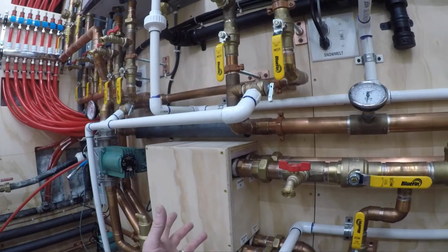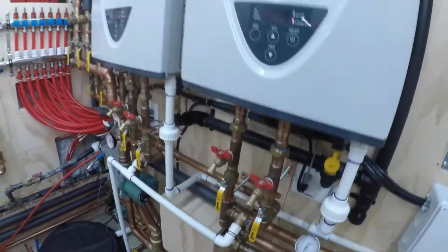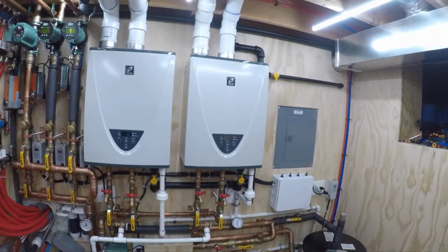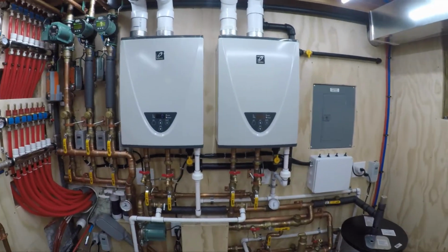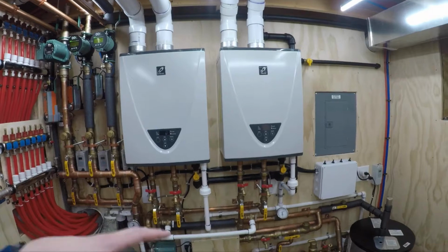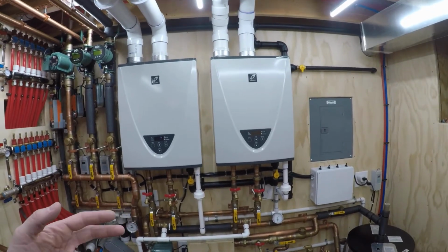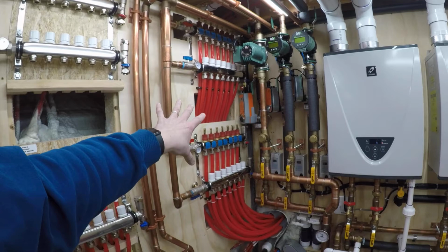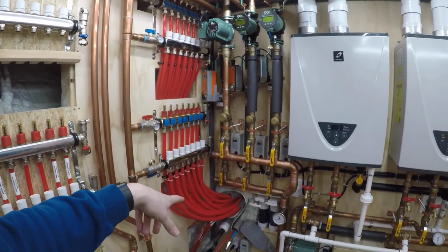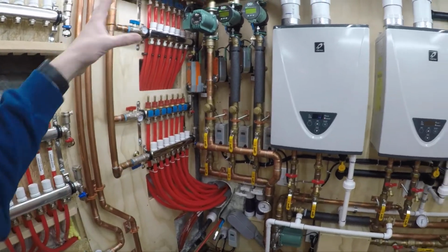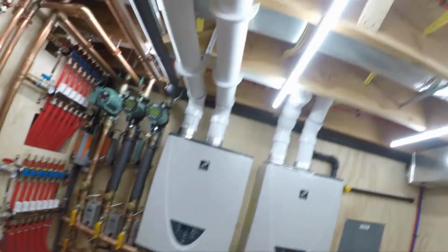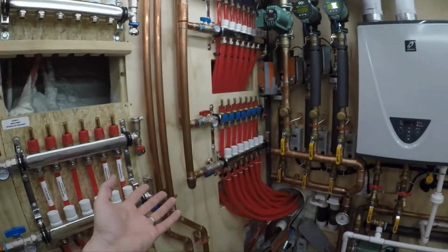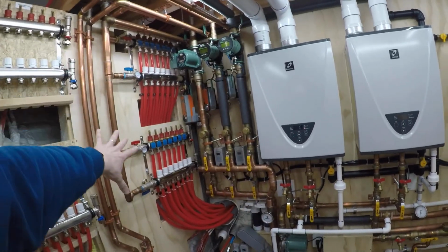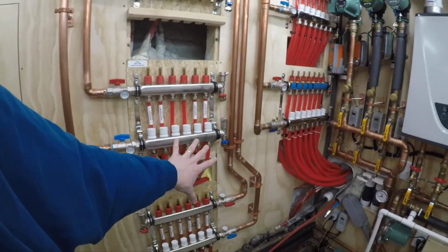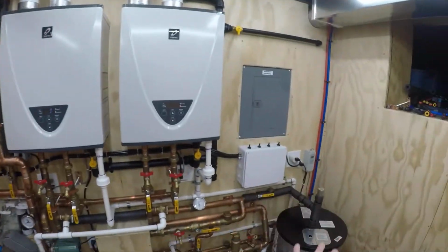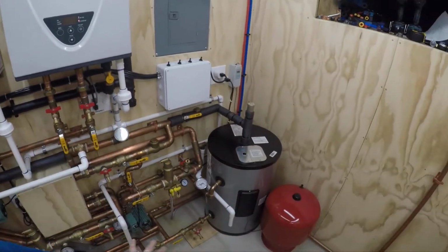So for those of you that don't know what a flat plate heat exchanger is, basically it's a mechanism that lets you heat up two different fluids without them mixing. Okay, because of the snow melt on this, I have to have glycol in the driveway or else it would freeze. I don't necessarily need it in the staple up in the house, but because this is all on that side of the flat plate, everything has glycol in it over here. Okay, but everything over here does not. This is all domestic hot water pretty much.